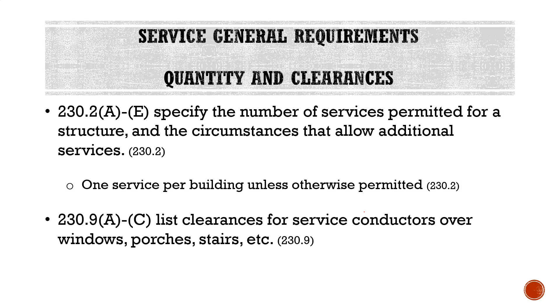Section 230.9A through C lists clearances for service conductors over windows, porches, stairs, and similar features — basically any type of dwelling or property you can imagine. When we're talking about overhead service conductors, this gives you how far away from that type of item or structure those conductors have to be.